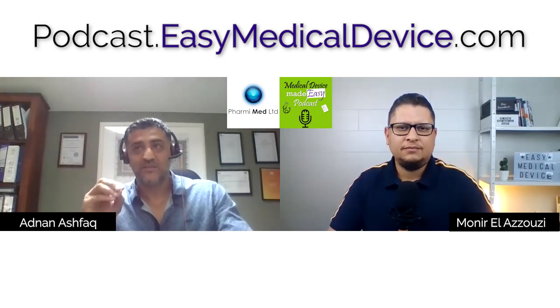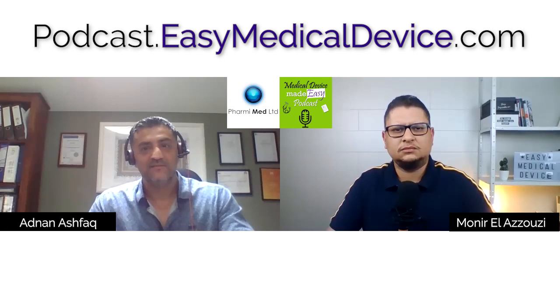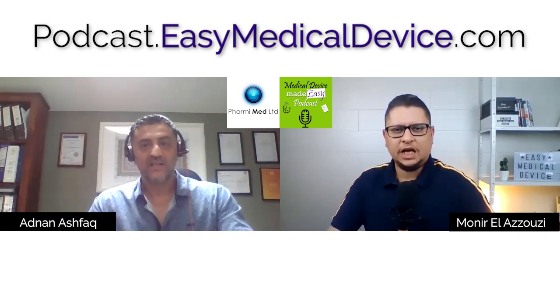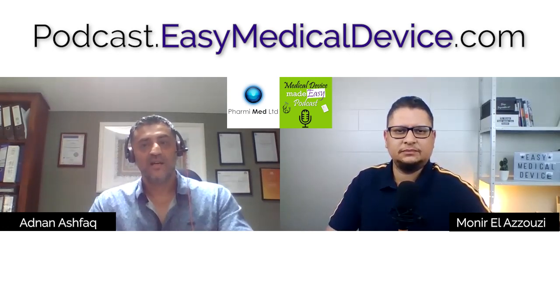And it's an excellent point, because I've come across some recent conversations where people have been confused with this. So not to be confused, there are two separate classifications for sure. So no doubt about that. First of all, there's the overall medical device classification, either a class 1, 2A, 2B, and class 3 in the European jurisdiction, or class 1, class 2, class 3 for the FDA. But let's concentrate on the European Union for CE marking. Once you have identified class 2A, B, or 3, or class 1, then we look at the safety classification, which 62304 then determines. But what it does is it automatically defaults your classification as a class C, which is the worst category, which means that your software can lead to a critical harm, such as death. It can actually lead to death. So serious deterioration of health, or serious injury or death.